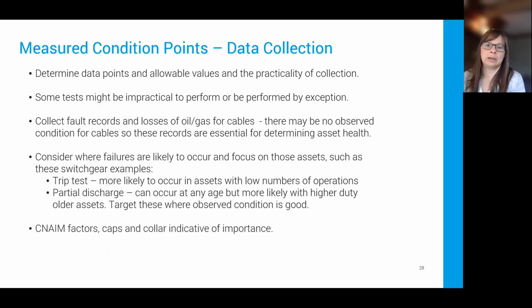Certainly in the UK, we do a lot of trip testing, and we do a lot of partial discharge, but we do relatively few IR tests and oil tests. They don't often come up in the data sets because they're not often collected by all the network operators. It's not always practical. So even though you see a data point in CNAIM, not every network operator will go and collect every single data point.